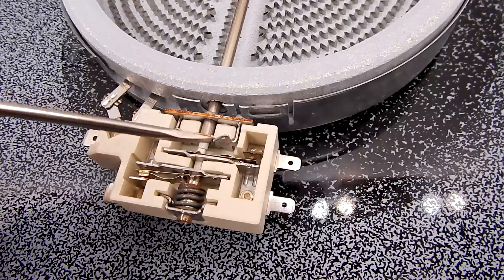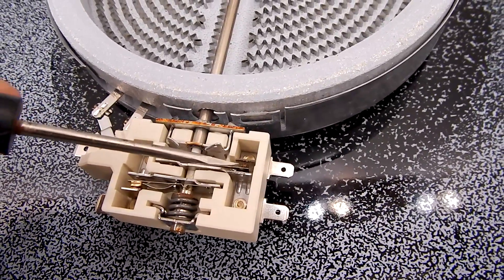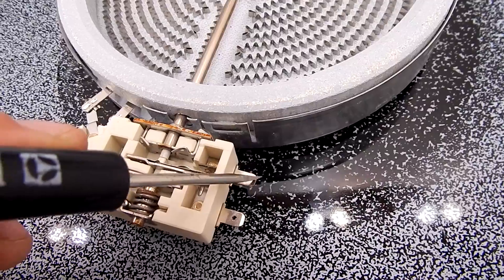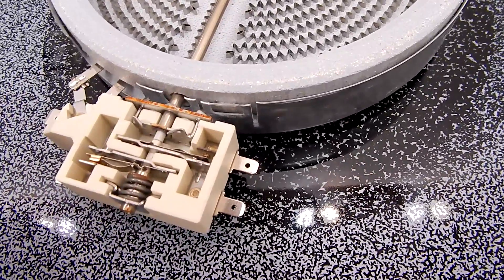As this burner starts to warm up just a little bit to where you wouldn't be able to put your hand on the glass without burning yourself, this little contact will open up and create a circuit from here straight through to here and go down to your hot surface indicator light. That's basically how one of those works.